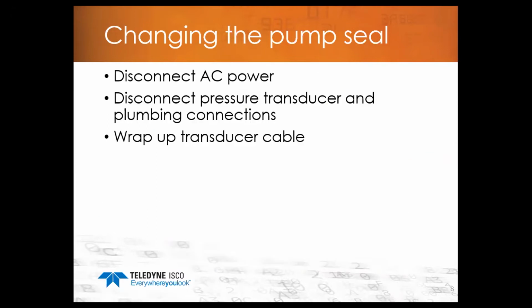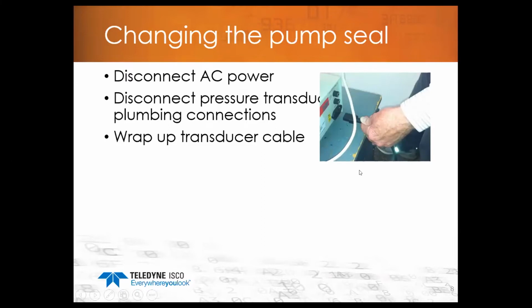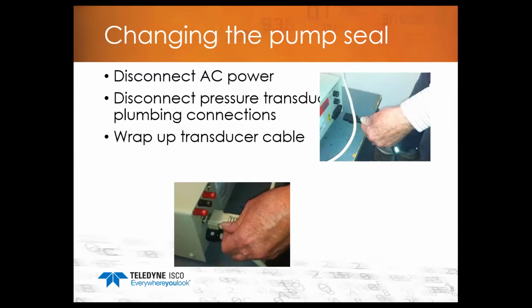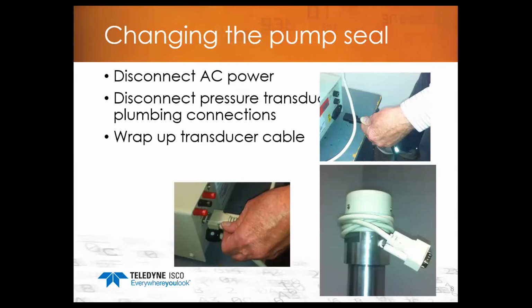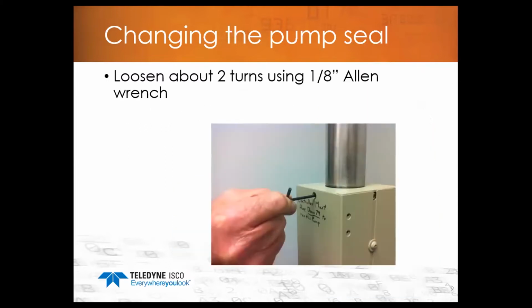So you'll want to disconnect your AC power cord from the back, and then you'll also want to unplug your pressure transducer cable from the back and just wrap it around the top of the pressure transducer cap at the top of the cylinder, just to keep it out of the way. So unplug your power cord, disconnect your pressure transducer cable from the rear, and then wrap your cable around the transducer, and at that point you'll be ready to remove the cylinder.